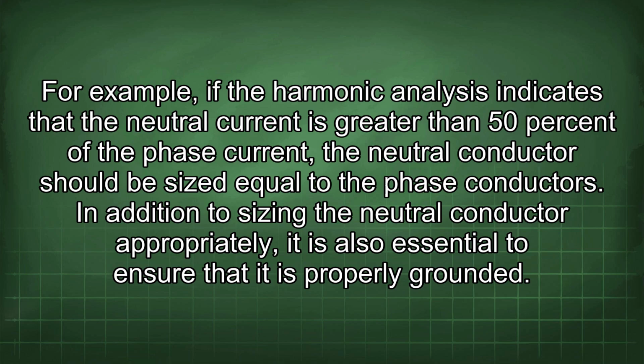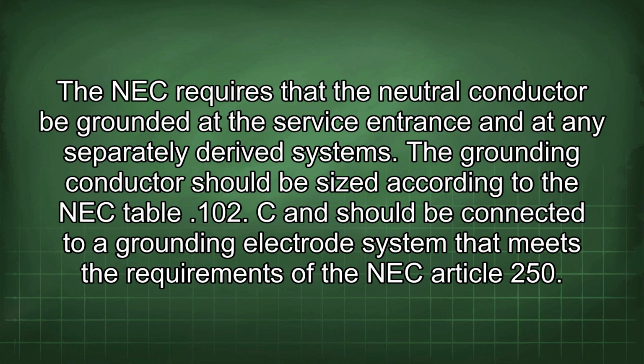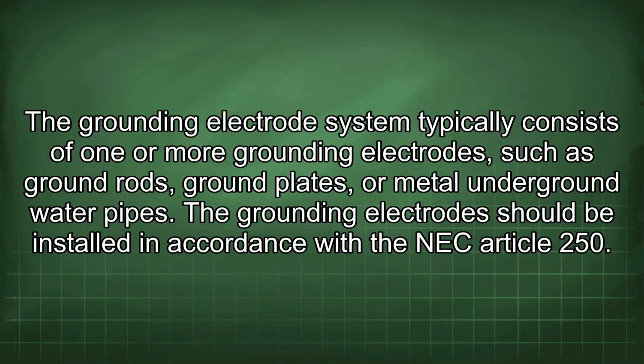In addition to sizing the neutral conductor appropriately, it is also essential to ensure that it is properly grounded. The NEC requires that the neutral conductor be grounded at the service entrance and at any separately derived systems. The grounding conductor should be sized according to the NEC table 102.C and should be connected to a grounding electrode system that meets the requirements of the NEC Article 250. The grounding electrode system typically consists of one or more grounding electrodes, such as ground rods, ground plates, or metal underground water pipes. The grounding electrode should be installed in accordance with the NEC Article 250.